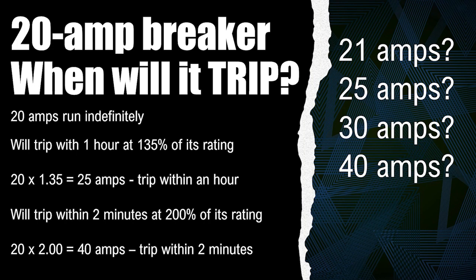This is really outside of my world — I don't manufacture products, I do not set the standards, I do not have to follow these standards. But I thought this was very interesting and I thought it would help you not only in understanding how circuit breakers work, but maybe in troubleshooting. If I've got a breaker — like a microwave — and it's tripping within two minutes, I know that current is at least 200%.